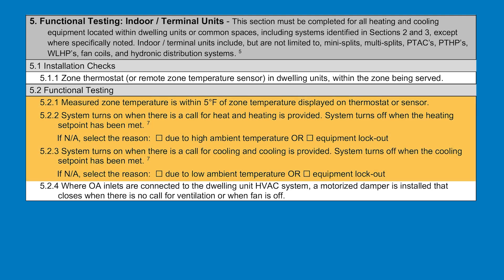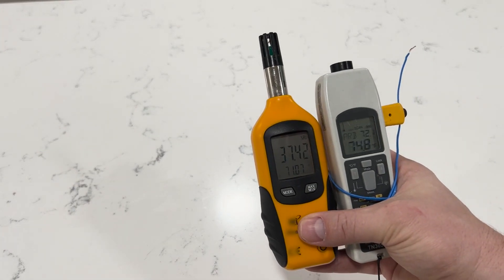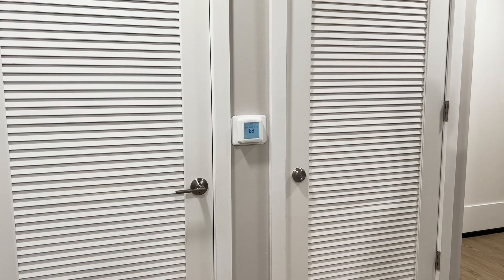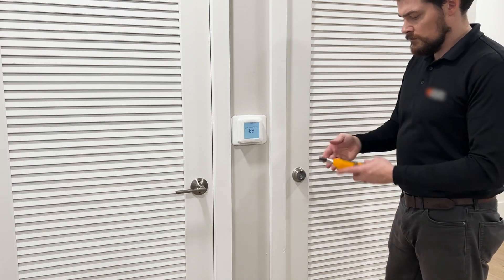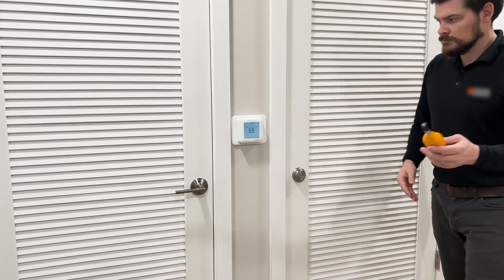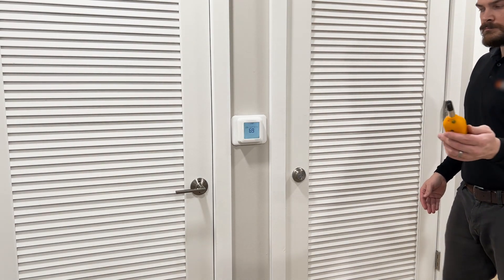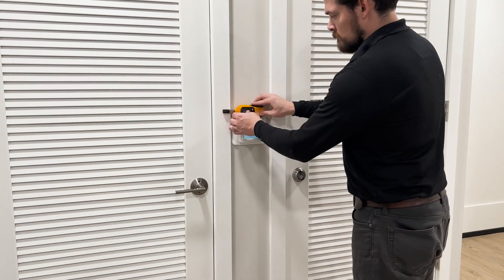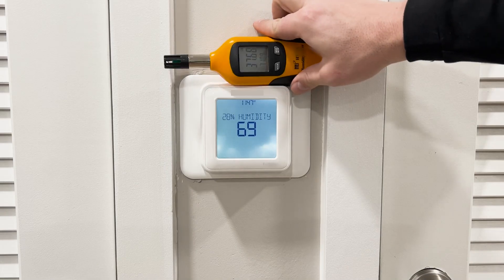For items 5.2.1 through 5.2.3, we are going to check that the thermostat is functioning correctly and measures the right temperature, and that it does indeed turn the unit on in both heating and cooling modes. To complete Section 5.2.1, we want equipment that is calibrated and can accurately measure the dry bulb temperature of the room, positioned about 4 feet above the floor, in the middle of the room, or near the thermostat or temperature measuring device.